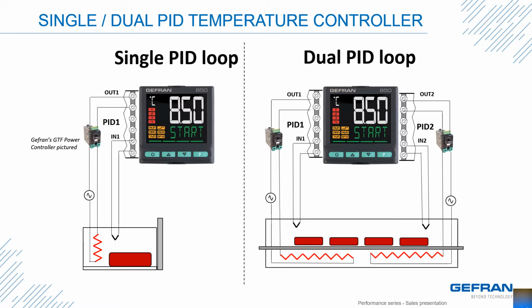Create a cascade control loop. There'd be a transformation in the picture on how the application would look, but it's a programming option to add that type of a feature. Watch actions on either loop and create strategies in the other, or this could be two independent control loops independently ramping and soaking.